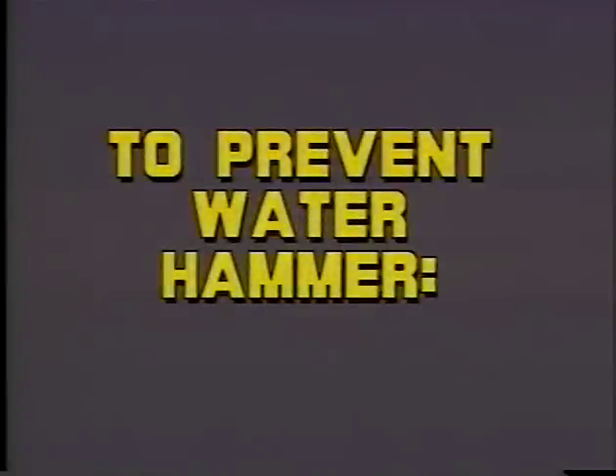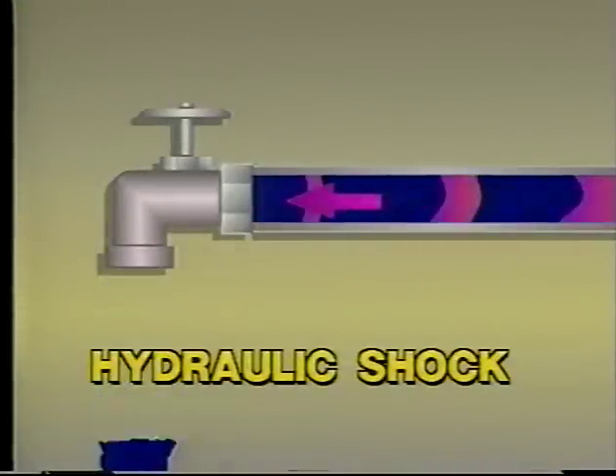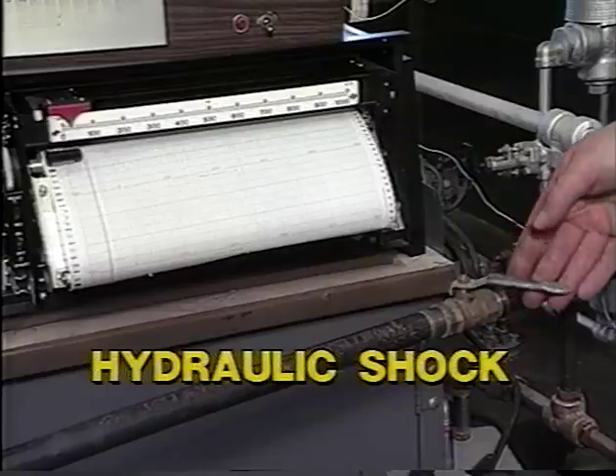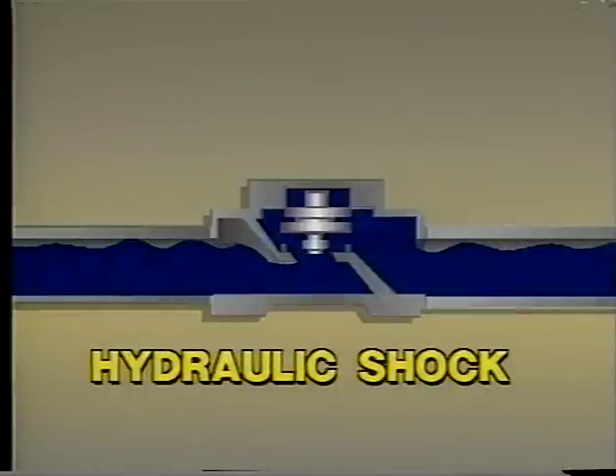Careful attention to these few guidelines will prevent most water hammer. Prevent the sudden stopping of water in pipelines by closing manual valves slowly, and by installing spring-loaded center-guided silent check valves where appropriate.